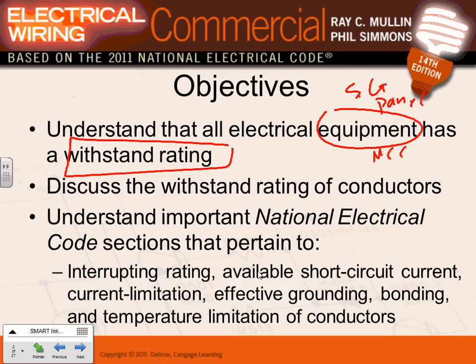What's a withstand rating? Let me give you a value. I have a 65 kiloamp withstand rating, meaning this switchgear can withstand, for a short amount of time, typically a couple of cycles, this amount of energy, heat, as well as this amount of magnetic field. Can I have a thumbs up, Chad? We fully understood that one. See how easy that is? Okay, this is withstand rating.